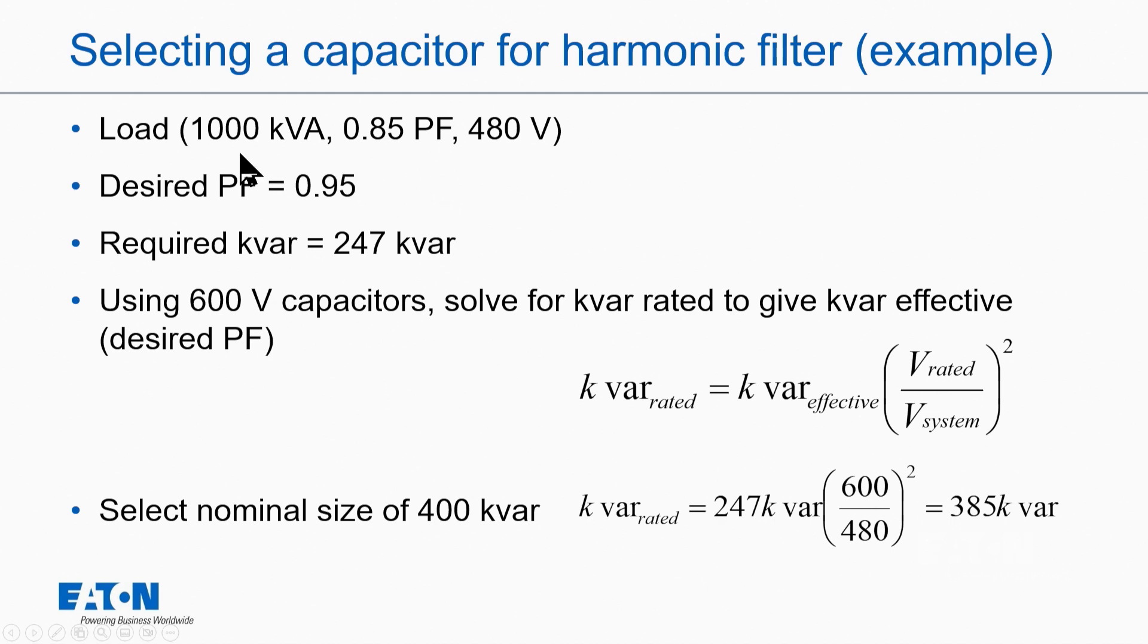So if I put in a load that's a thousand kVA, 0.85 power factor, and my desired power factor to eliminate my penalty will require 247 kvar. In order to use the higher rated voltage caps, I put that 600 here on this side of the equation.